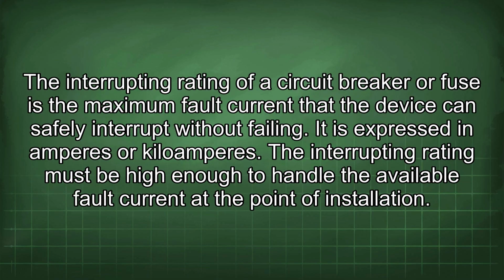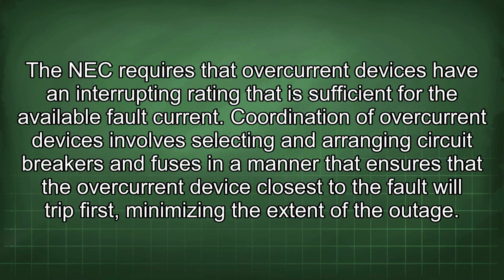The interrupting rating of a circuit breaker or fuse is the maximum fault current that the device can safely interrupt without failing. It is expressed in amperes or kiloamperes. The interrupting rating must be high enough to handle the available fault current at the point of installation. The NEC requires that overcurrent devices have an interrupting rating that is sufficient for the available fault current.